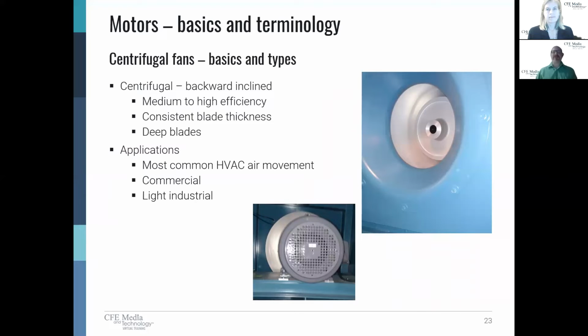The backward inclined centrifugal, the workhorse of the centrifugal fan. So what makes this excellent is that our fan blades are actually bent backwards. So we have about 80% efficiency, whereas opposed we were down in maybe the 50s or 60s with, say, radial. And the air leaves at very low velocity from the blades as a result, which means we can generate high pressure, but we also have very low noise.